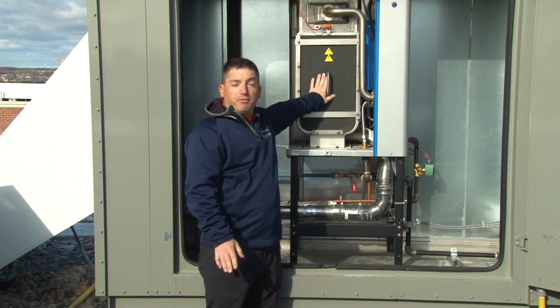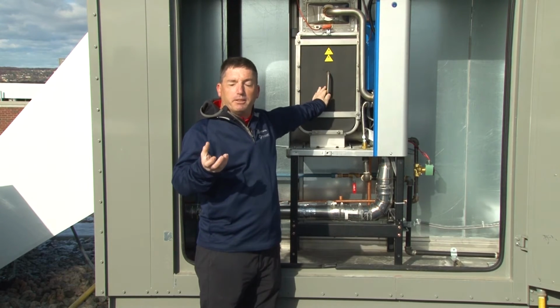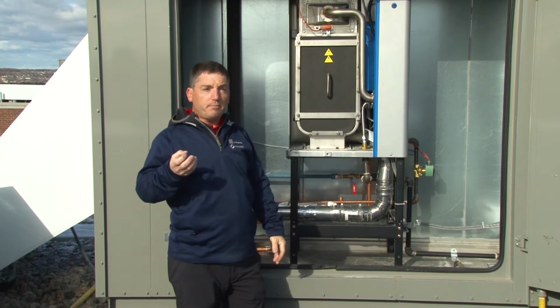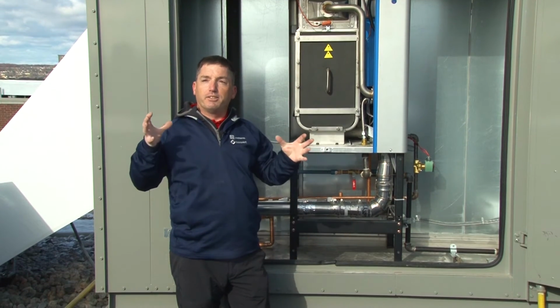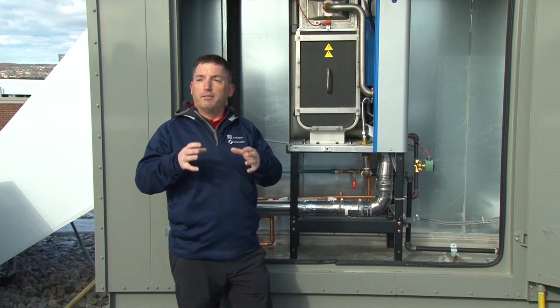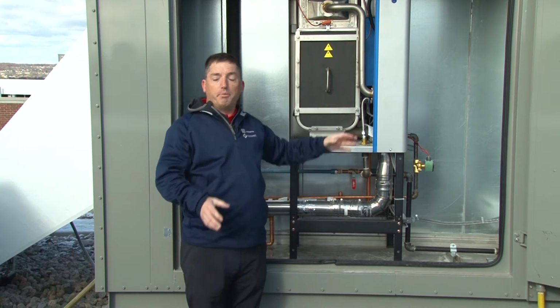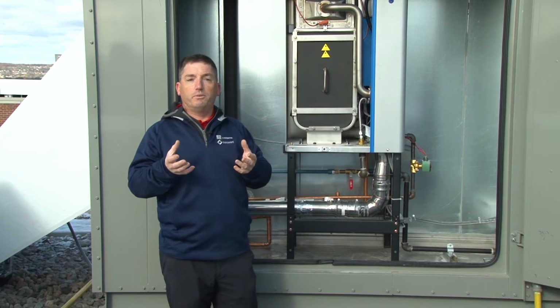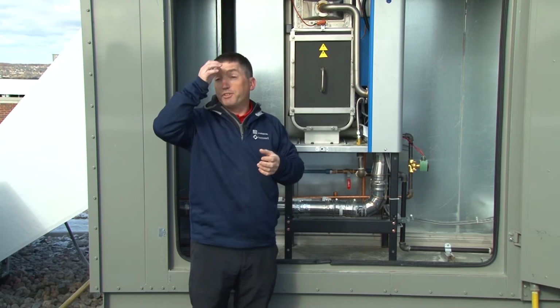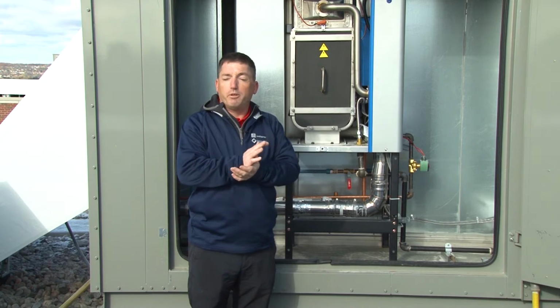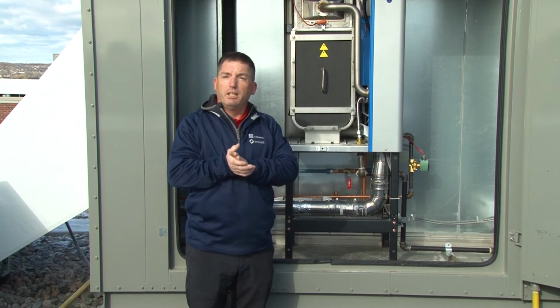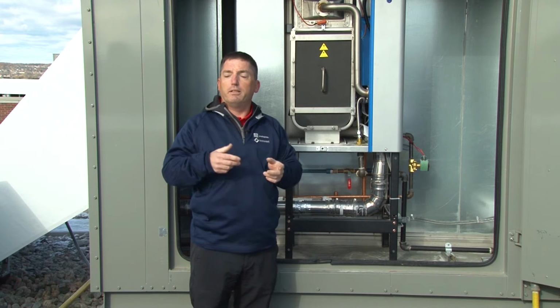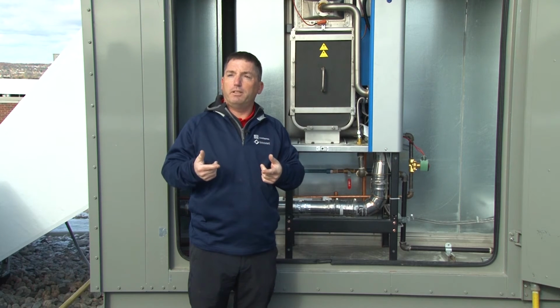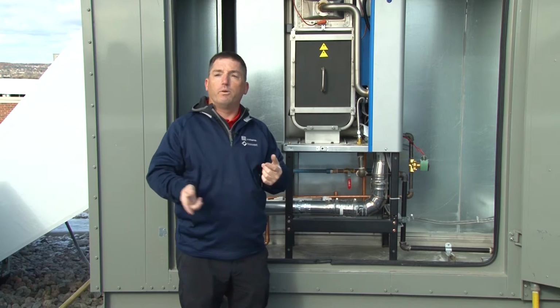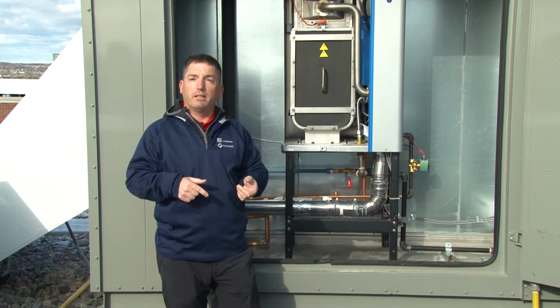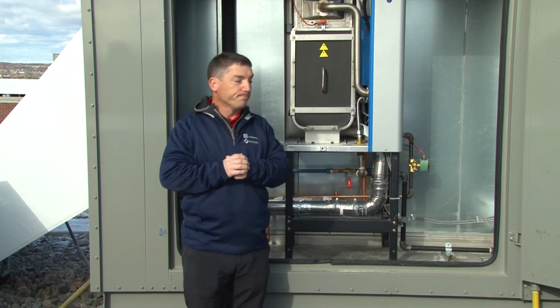The issue with a humidifier is the element that you're using to boil the water. Obviously, that has to get hot. That is going to then attract the leftover minerals. So what's going to happen is the heat exchanger inside is going to collect those in the form of surface scale. What I always tell people is, just like your filters, it's always easier to clean it more frequently and stay ahead of the scale buildup rather than letting it go an entire season and then trying to clean it at the end, because it will be virtually impossible.